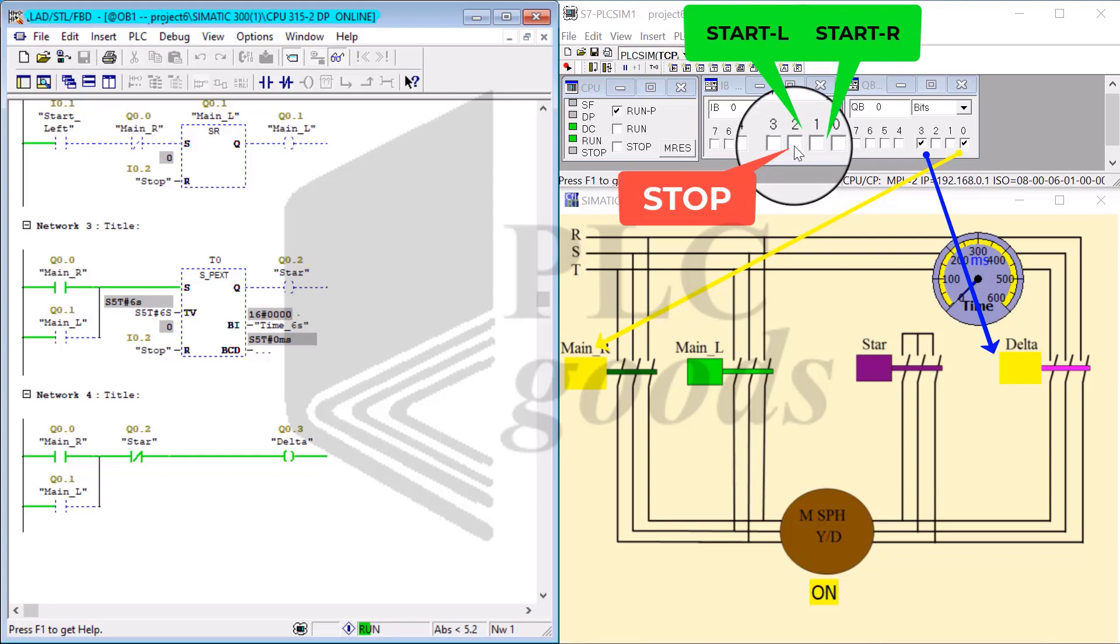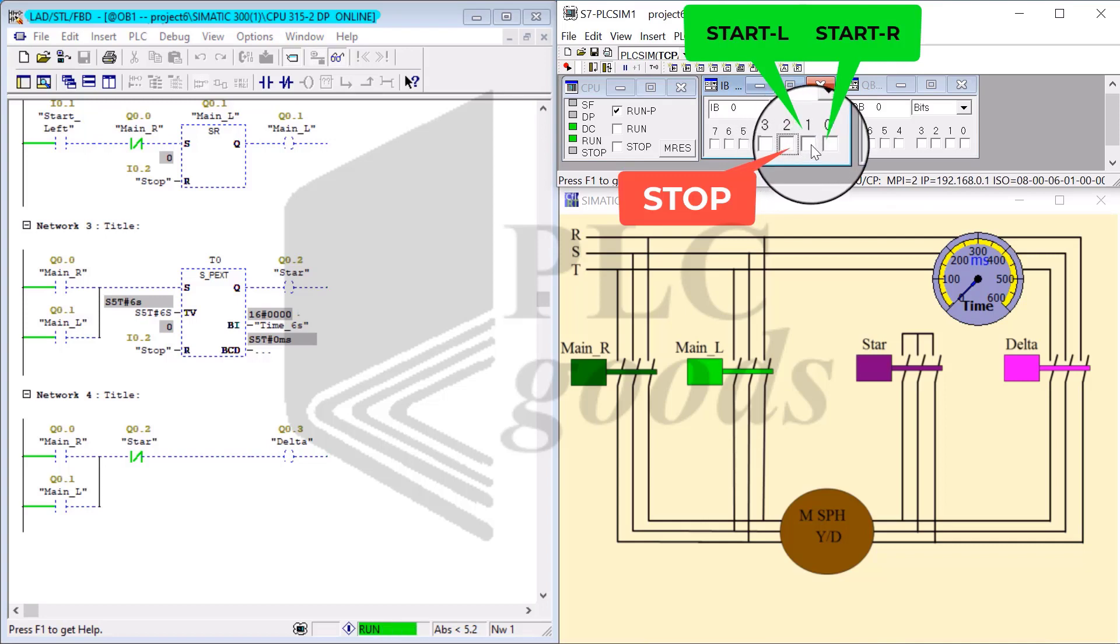I go ahead and stop the circuit again, and this time I tap on start left. After six seconds, delta kicks in.